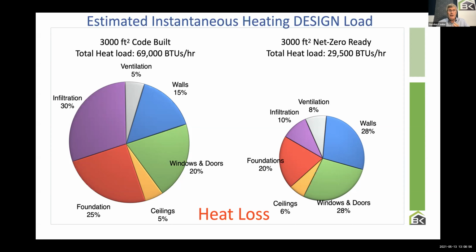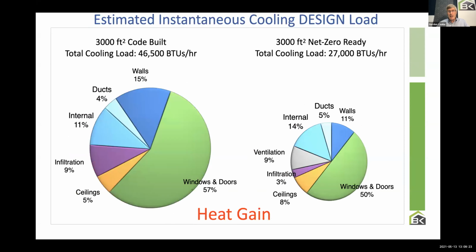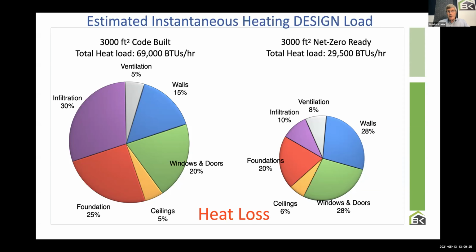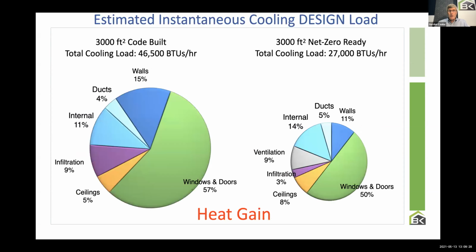And so look at the difference on those houses. A house built to the typical code today, a 3,000 square foot house, would need 69,000 BTUs, which is a pretty darn good number, a pretty low number. But by the time we get to net zero ready, I only need 29,000 or 30,000 BTUs, basically half the size. You can say, well, that's pretty much the same as the energy. The energy was half the use. And it is useful to see that the estimated design heating load is roughly half.